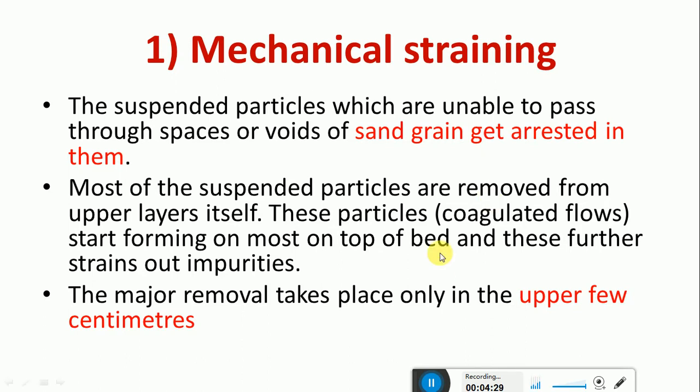Most of the suspended particles are removed from the upper layer of the sand itself. These particles start forming on top of the bed, and it further strains out the impurities. The removal takes place only in the upper few centimeters of the sand. This is called mechanical straining. That means due to the straining action, the filtration takes place.